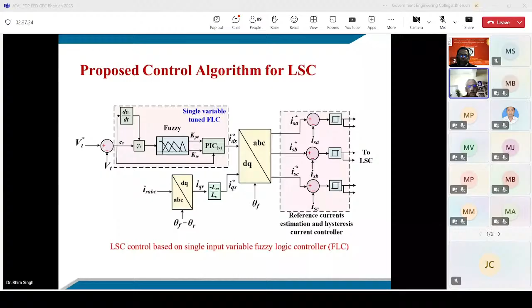At synchronous speed, it passes through synchronous speed. You can understand synchronous speed - we don't give any reactive power, we give a DC current into it, similar to a conventional synchronous machine. So that's the concept of voltage control.